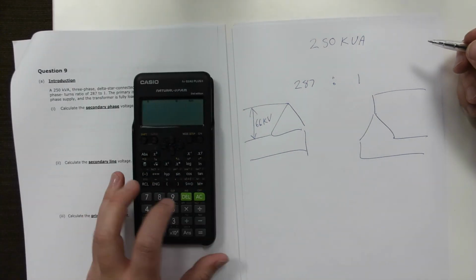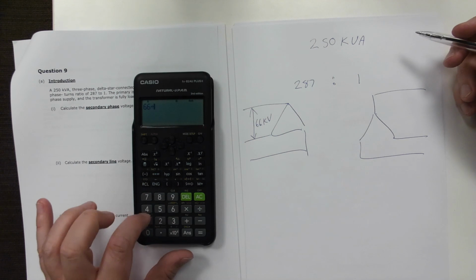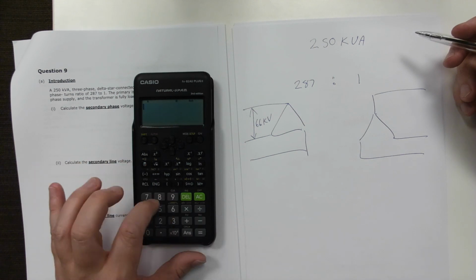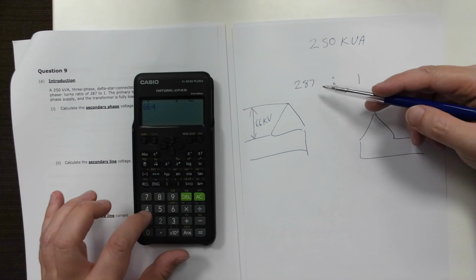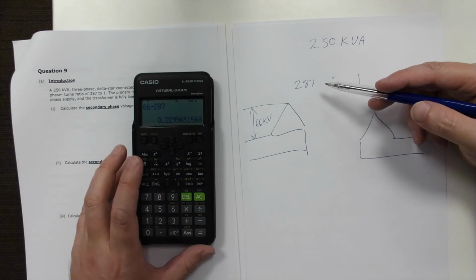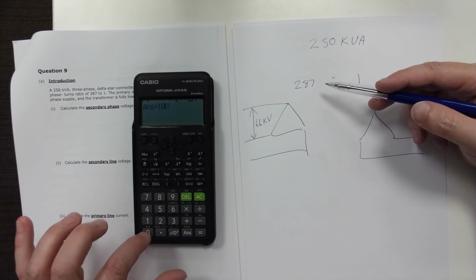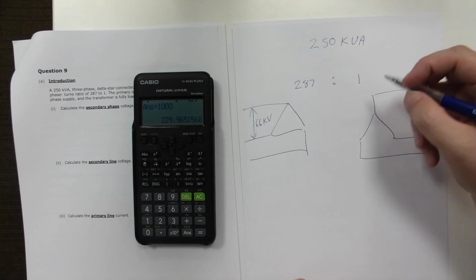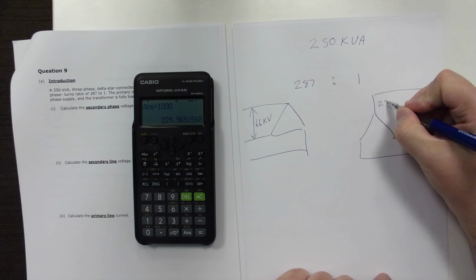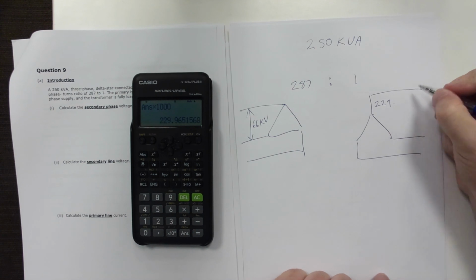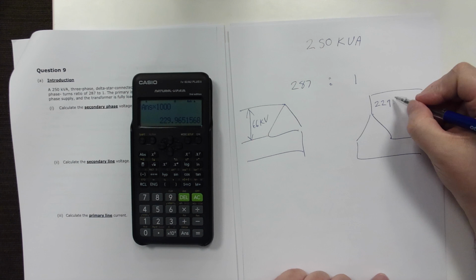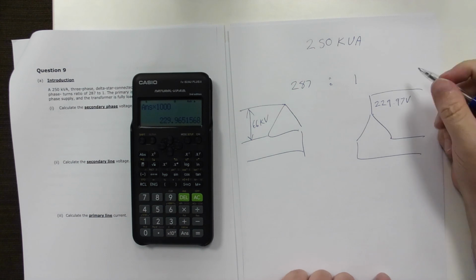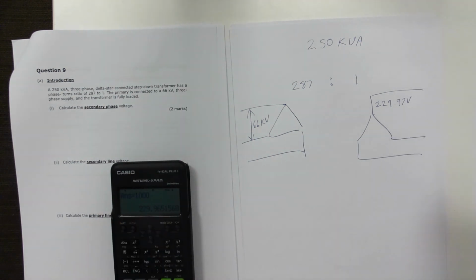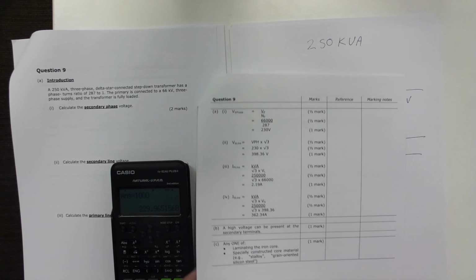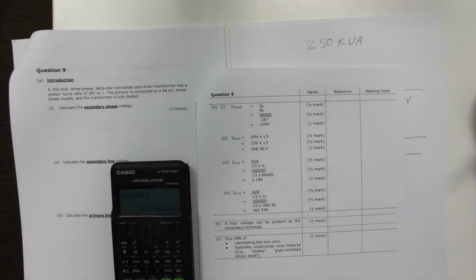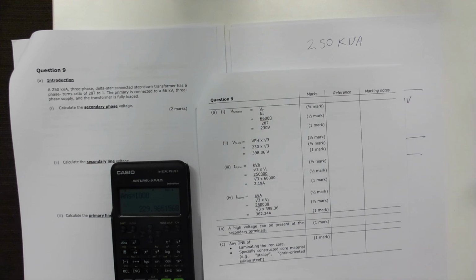So all we have to do is go 66 divided by 287, and then times by 1000, because it was kV, and we get 229.96, so 229.97 volts. And if we look at our answer sheet, they gave us 230 volts. So they didn't do to 2 decimal places, but same deal, same calculation.